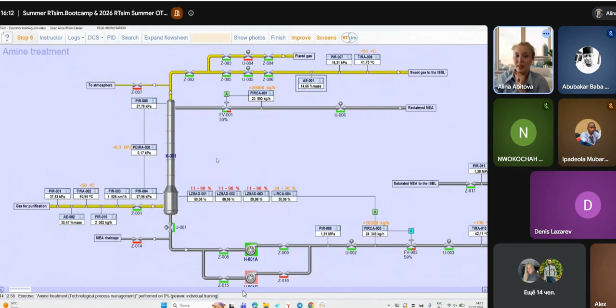This is a safety rule. Let's say it may happen that two devices show correctly and one is broken. And then the majority decides. So if two devices show emergency values, this means that an emergency happened, and the entire installation must be blocked. But if the majority of devices tell us that everything is normal, then everything is normal. So usually in plants, it's three or five devices which show us an emergency situation. I've never seen seven, but it can also be, I guess, maybe just in my experience it didn't happen. Usually it's three or five. Yeah, so we have here three devices.